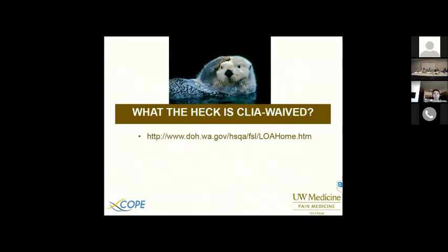Here's my little critter that triggers my blurb on CLIA waived. You need to have training. You need to train your staff to be able to do this. And essentially what the Department of Health is allowing you to do is to do some laboratory work in a non-formal laboratory setting. But there are some stipulations, and the stipulation is that it can't be the be-all and end-all test. If you find something here that you need to follow up on, you need to do it with other technology. You shouldn't make significant clinical decisions which result in other testing or, for instance, in our case, dismissal from opioid prescribing based on this test.